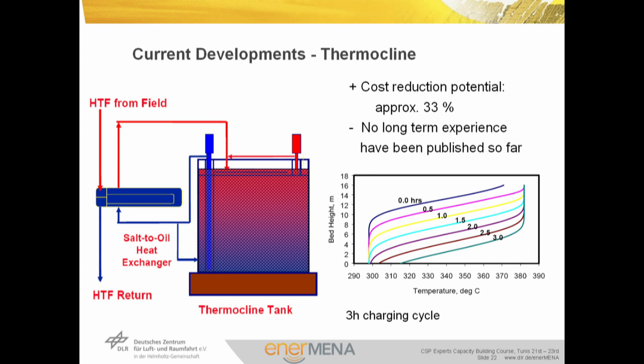An alternative to reduce costs is to replace part of the molten salt with a cheaper filling material — the so-called thermocline approach. Here, a solid material is filled into the storage tank, replacing part of the molten salt. The cost reduction potential is considered to be about 33%. While this approach has been demonstrated in experiments, there is no long operational experience available so far.